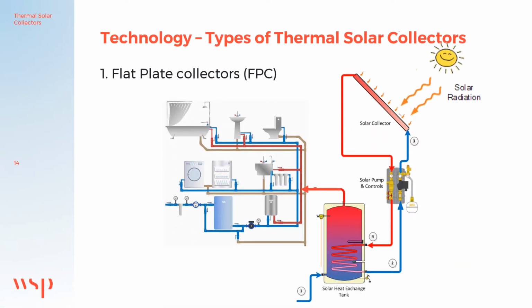There are many different configurations for FPC systems, but the most common configuration is to circulate the hot liquid from the solar collector through the hot water tank. A heat exchanger is used. The hot liquid from the solar collector does not mix with the hot water in the tank. FPC is simple and proven technology with a good cost-performance ratio and is readily available. There are no moving parts and it is easy to install on the roof and ground surfaces.